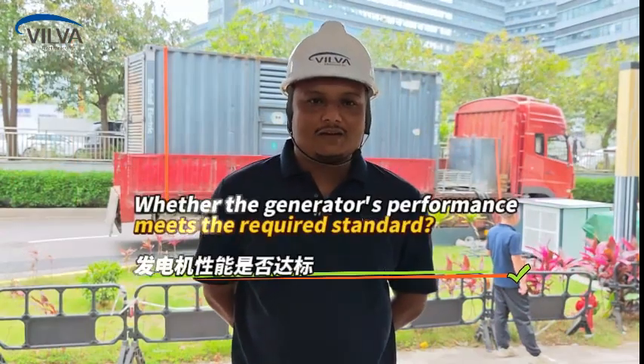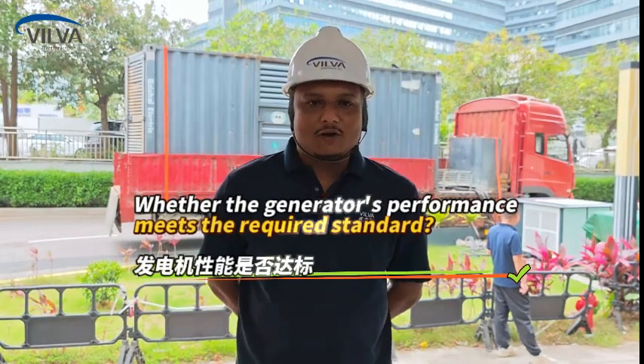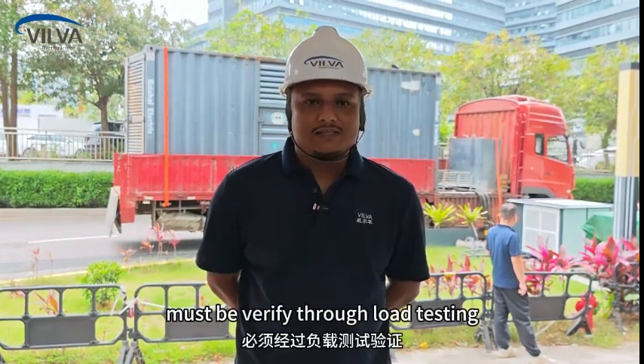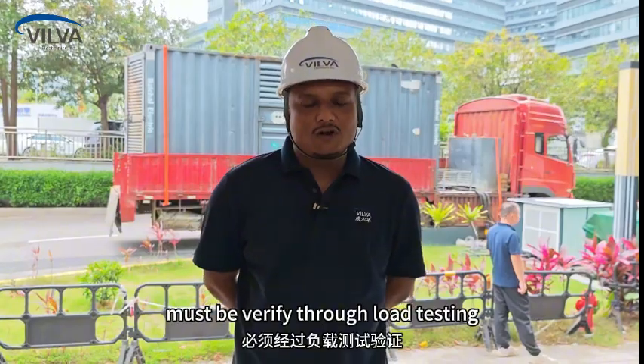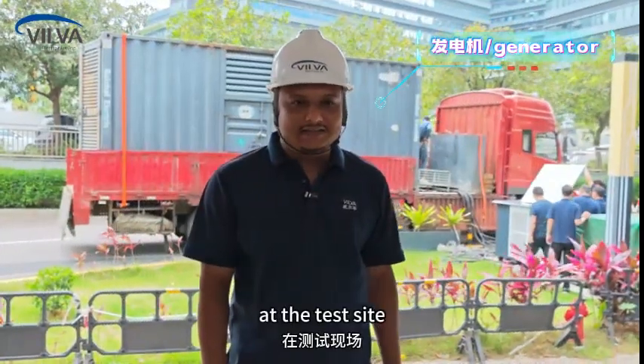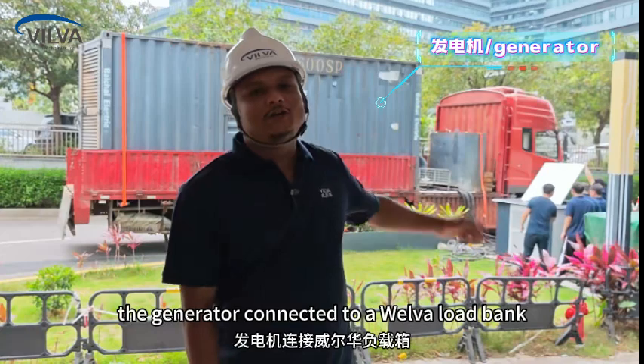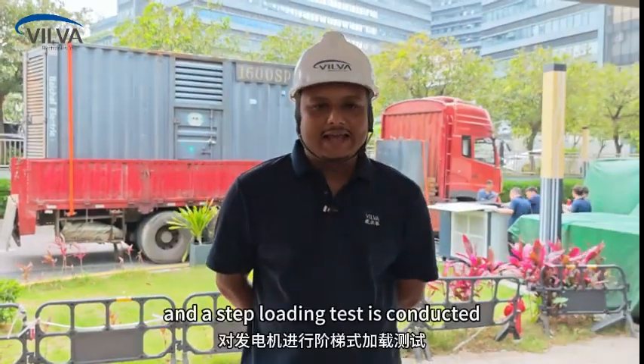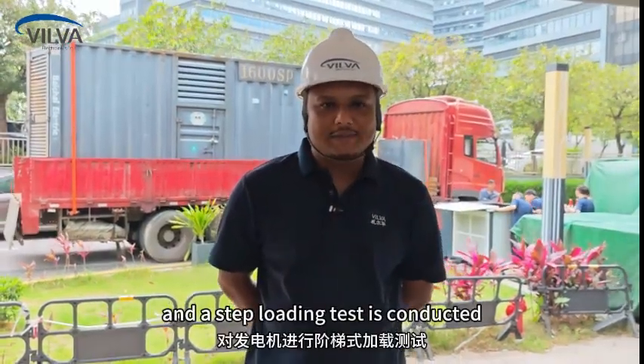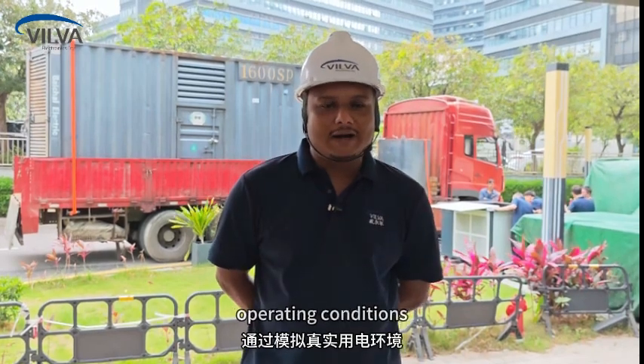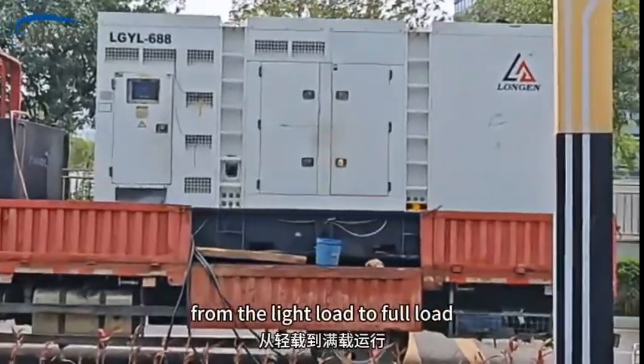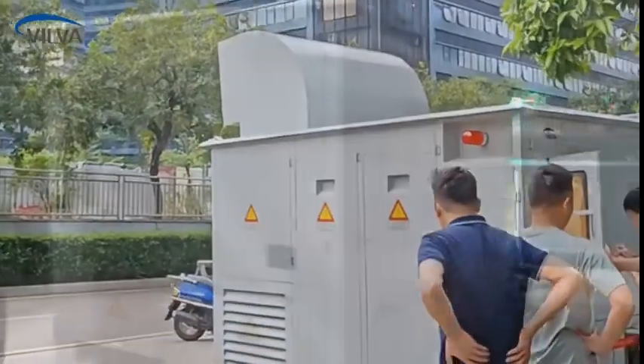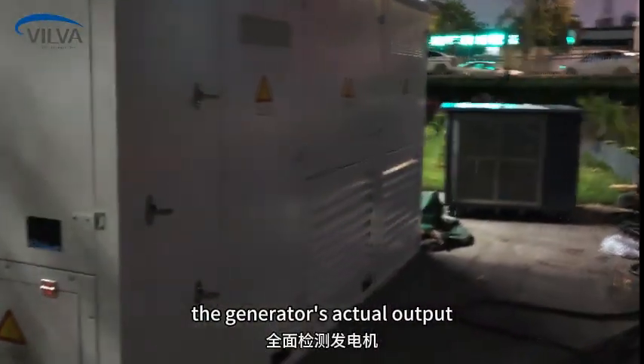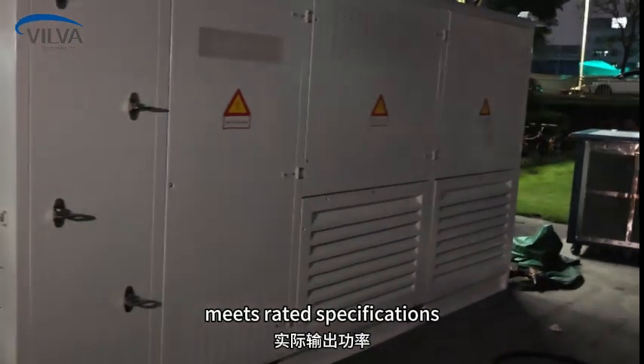Whether the generator's performance meets the required standard must be verified through load testing. At the test site, the generator is connected to a VILVA load bank, and a step loading test is conducted by simulating actual operating conditions from light load to full load to verify that the generator's actual output meets rated specifications.